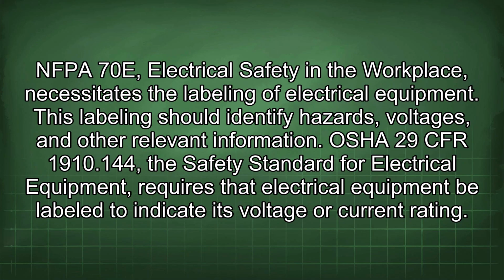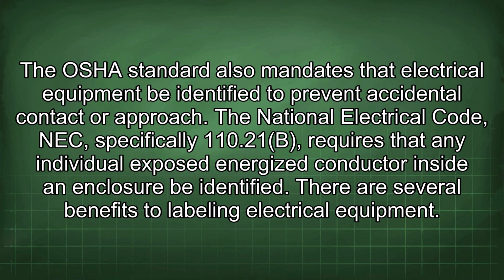NFPA 70E Electrical Safety in the Workplace necessitates the labeling of electrical equipment. This labeling should identify hazards, voltages, and other relevant information. OSHA 29 CFR 1910.144, the safety standard for electrical equipment, requires that electrical equipment be labeled to indicate its voltage or current rating. The OSHA standard also mandates that electrical equipment be identified to prevent accidental contact or approach.